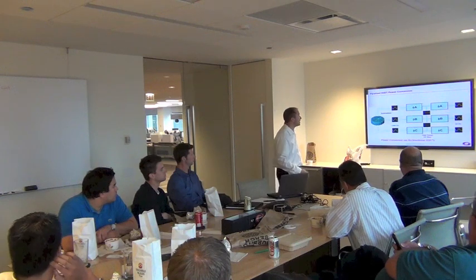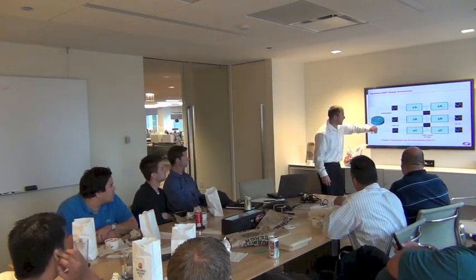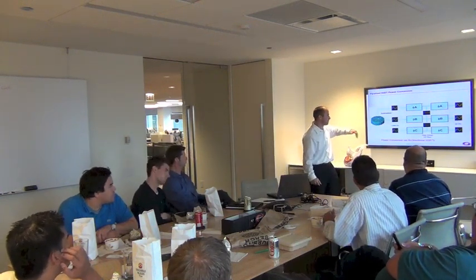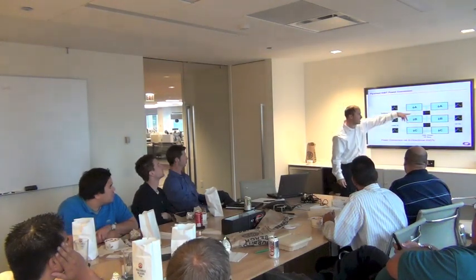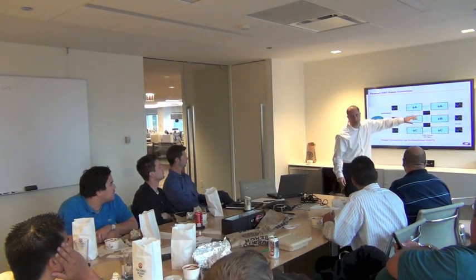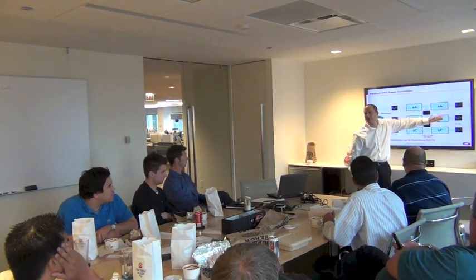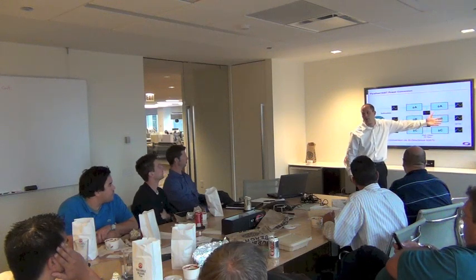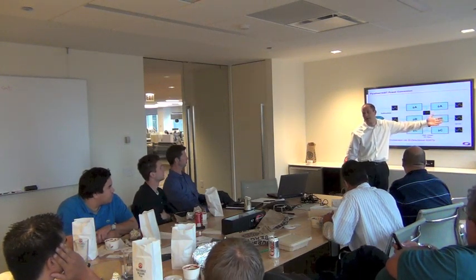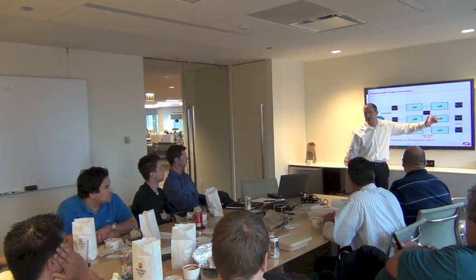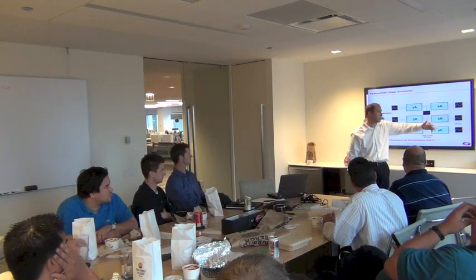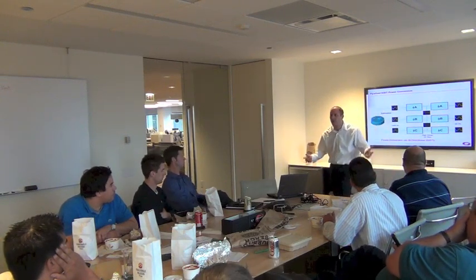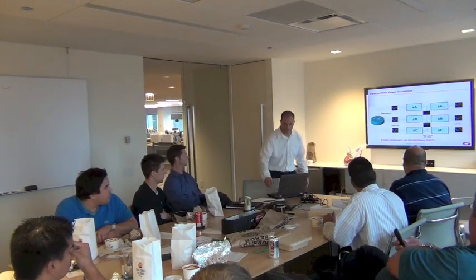So this is just a high-level drawing of our bidirectional power converters and our flywheels. We come out of our flywheel at about 1,000 hertz, convert to about a 785 DC bus voltage, and then 480 volt 60 hertz if you're in the U.S. We also do some 400 volt 60 hertz applications in the U.S. We've seen a little bit of a trend in that area, mostly in the data center arena. Obviously, we have 400 volt 50 hertz as well, depending on where you are in the world.